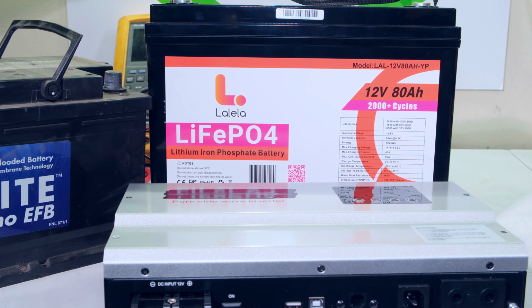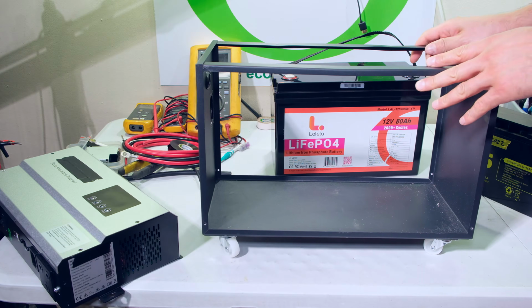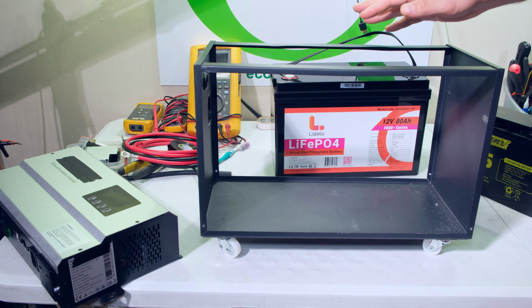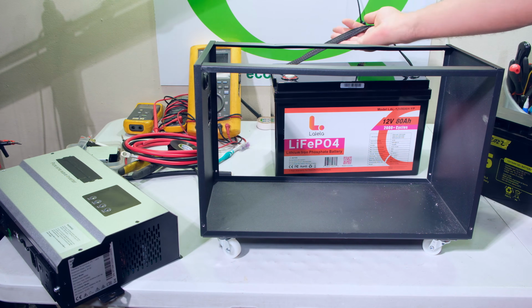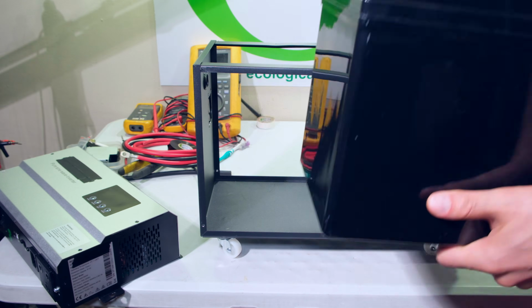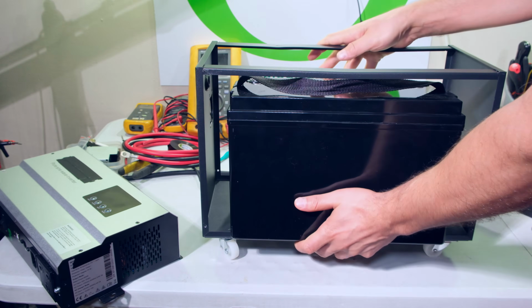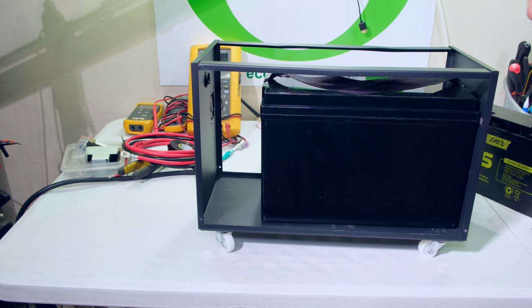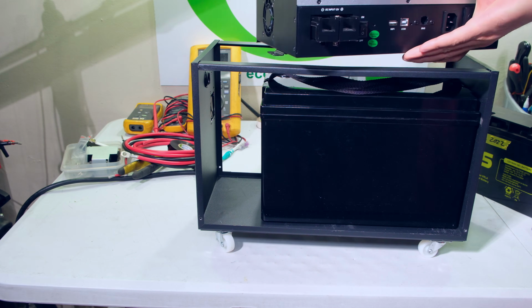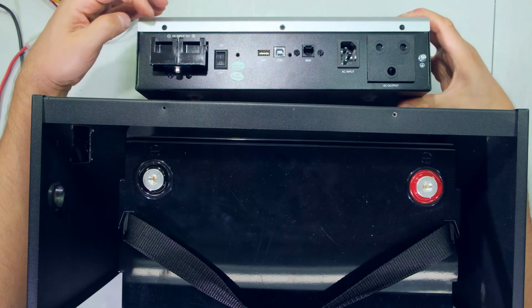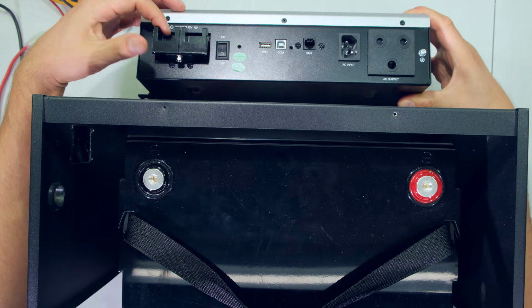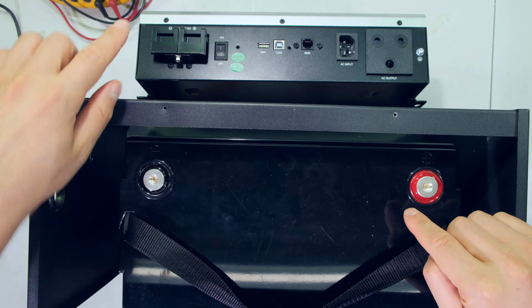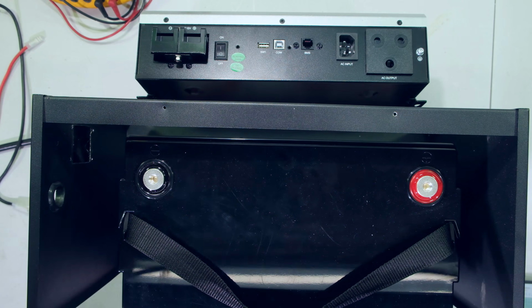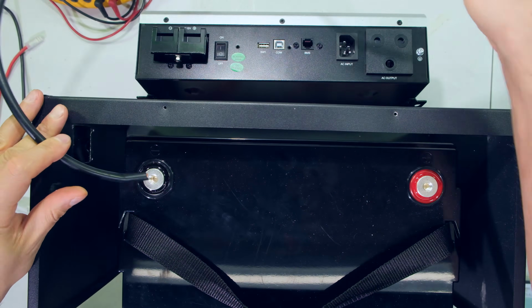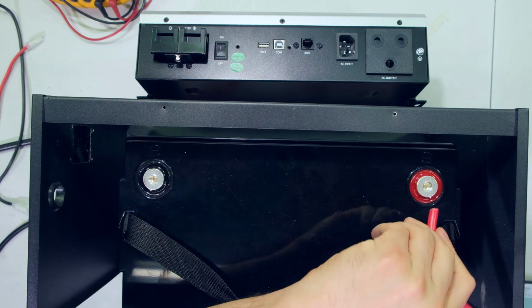So now what I need to do is determine the protection that I'm going to use for this application. Now I'm going to put the battery in a cage so that there's no access to the terminals. And that's the first step in making a safe solution. So I'm just going to put this inside here. So I will have a cover, and then my inverter would probably sit on the top. So just say, for example, it's something like this. All right, so here's the inverter. I've got the positive and the negative. So I need to wire the battery's positive and negative to the inverter. So say, for example, I use this wire. I would wire from there to there, and then the positive I'd wire from there to there.